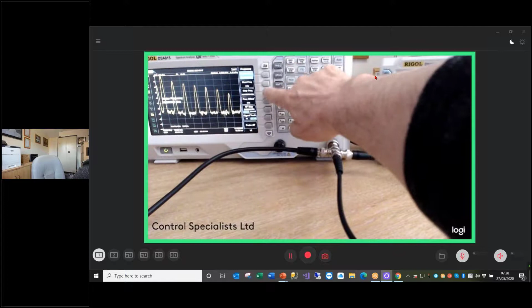So therein lies the issue. This is what a drive, amongst other things, is doing. It uses pulse width modulation on the output of the drive to basically switch something in the order of 600 plus volts on and off. There's your square wave. The rate it does so is roughly between 2 and 20 kilohertz, but the actual harmonics generated, moving off into the distance, can go up into the megahertz. That's just a function of what they do.